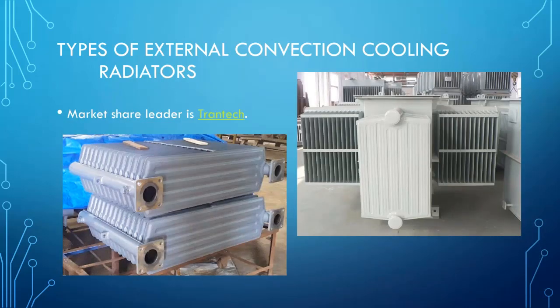And here are the radiators. They're made by several different manufacturers in the US and abroad. And I believe Trantec is still the market leader on these. They're available in mild steel, stainless steel, galvanized. And of course, the transformer manufacturer has to order these from Trantec. And I don't want to speak out of turn, I just don't know of a transformer manufacturer that manufactures their own radiators. But Trantec is very, very good at this. They've been doing it a long time. They have all the certifications, and it's a very, very good product and very effective at cooling.